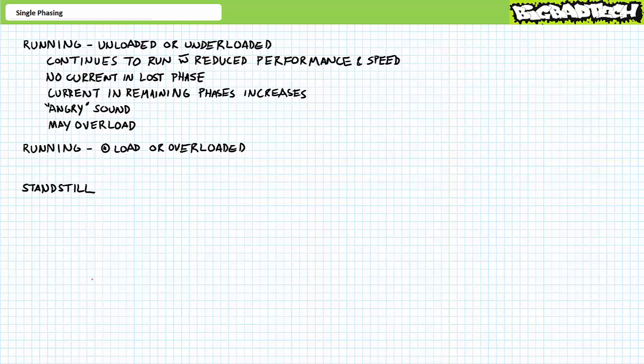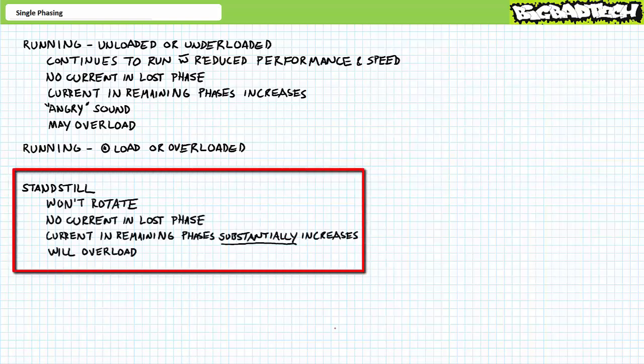In contrast, a motor single phased at rest might not even start rotating, because the loss of a single phase means the rotating magnetic field produced by the stator is not properly established. Given motors at rest experience a large surge of inrush current, with the rotor locked in place, current drawn by the remaining phases will be many times rated current. This motor will quickly enter an overload condition, and lacking overload protection, will rapidly damage or destroy itself.